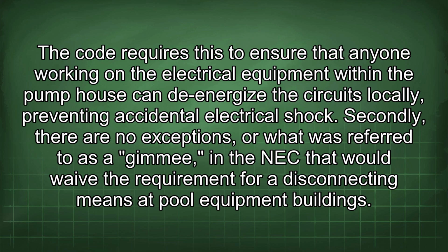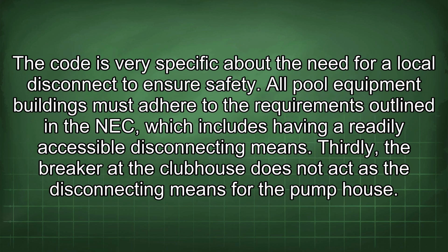Secondly, there are no exceptions, or what was referred to as a gimme, in the NEC that would waive the requirement for a disconnecting means at pool equipment buildings. The code is very specific about the need for a local disconnect to ensure safety. All pool equipment buildings must adhere to the requirements outlined in the NEC, which includes having a readily accessible disconnecting means.